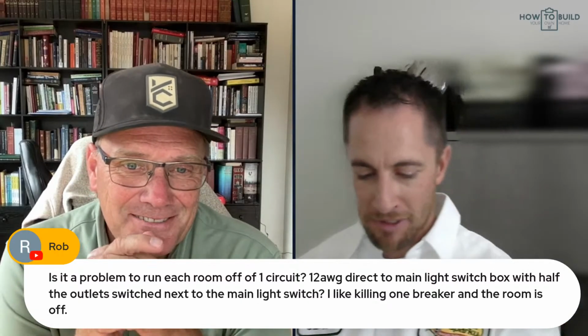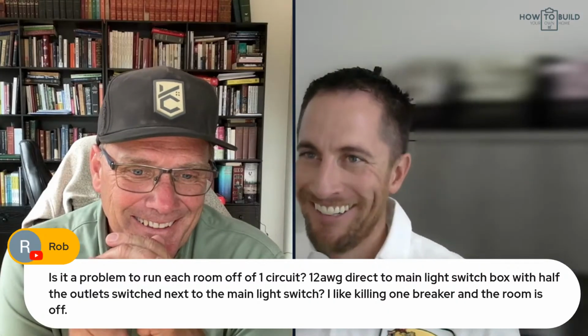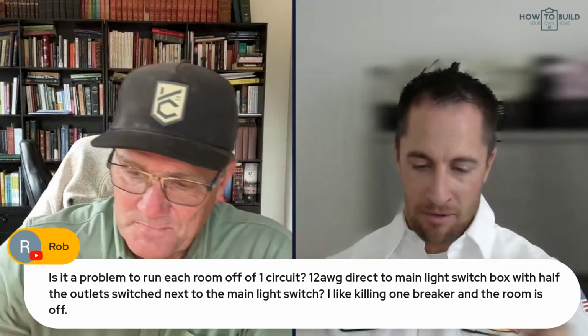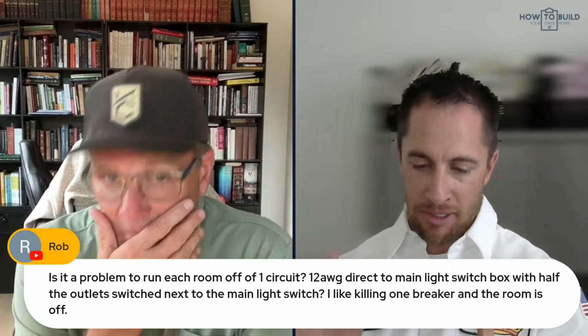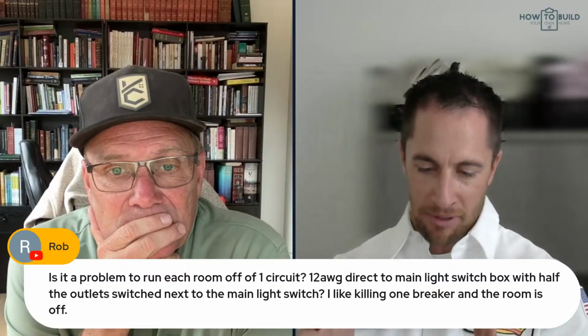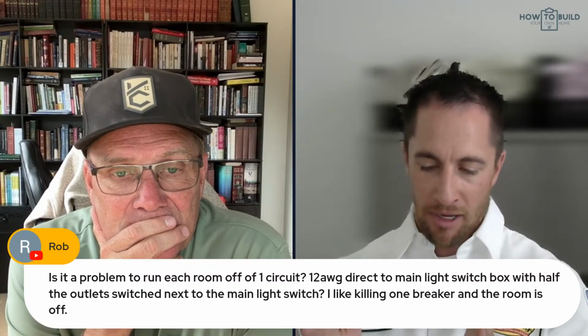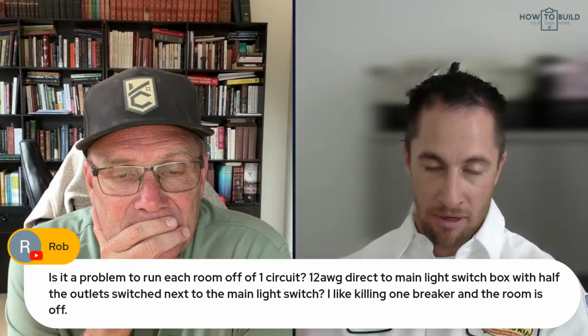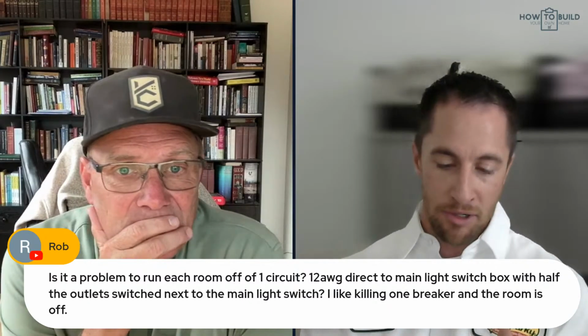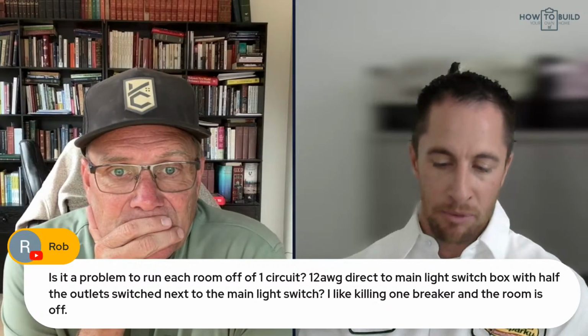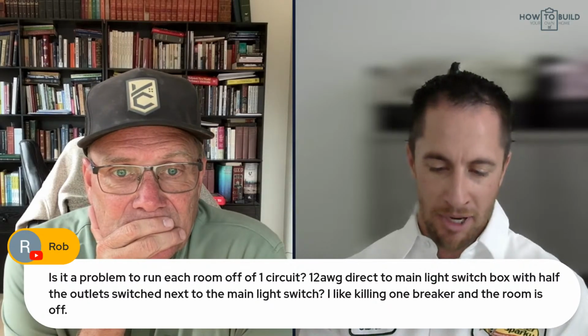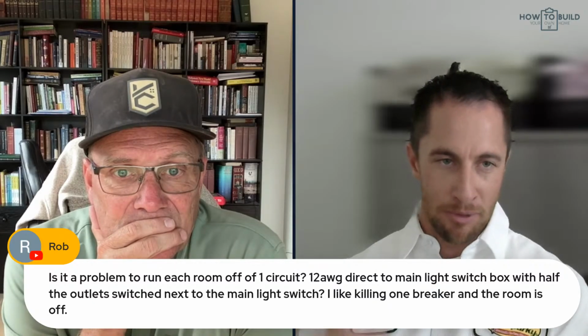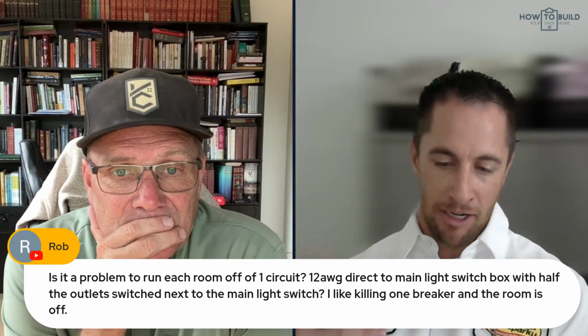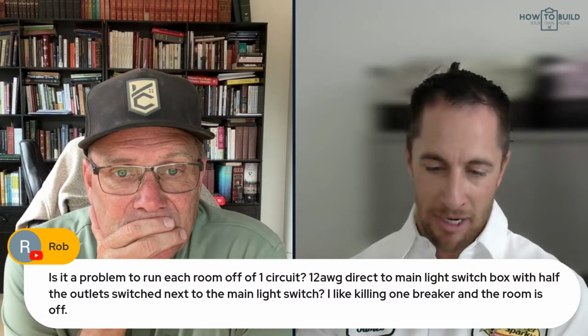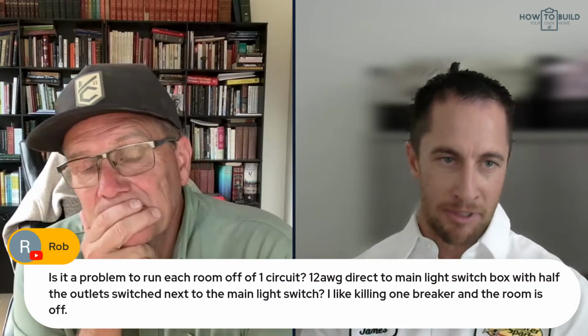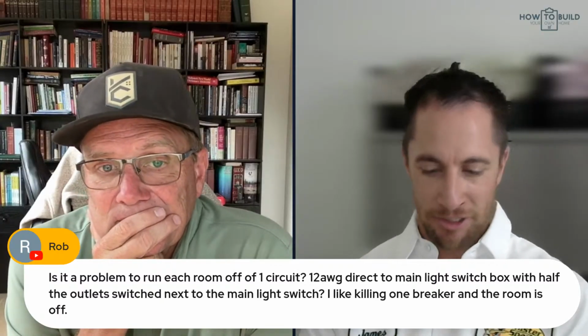I'm going to start with explaining what a GFCI is for. All a GFCI is doing is making sure the same power that is coming to the receptacle is the same amount of power that's coming out of it on the neutral. If there's a difference of 5 to 20 milliamps, which is not a lot of power, it's going to trip. You want it to trip. To give you an idea, if you get hit with 10 milliamps at 120 volts, you're going to feel a pretty good tingle. At about 20 milliamps, you're really going to start feeling it. And I want to say it only takes about 25 milliamps to stop your heart. So the point is for safety.